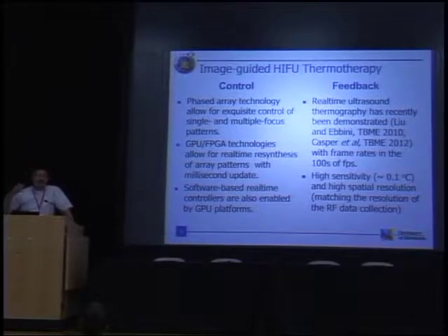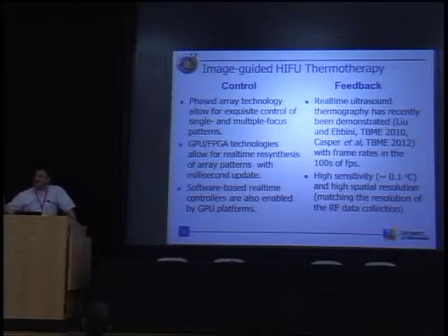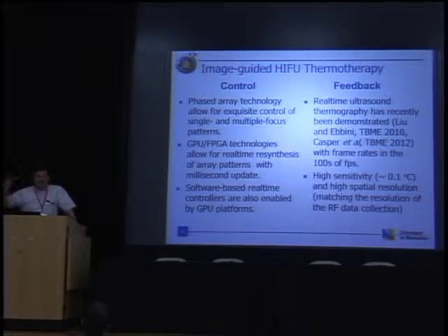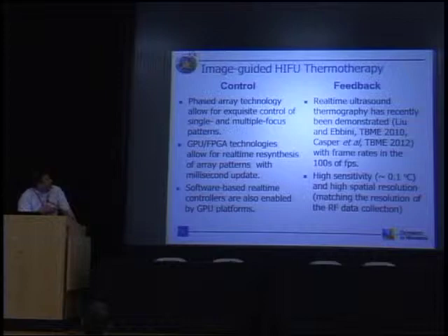We developed these nice algorithms for refocusing arrays, but the circuitry, just simply the error in quantizing amplitude and phase, for phased arrays was larger than anything you can hope to correct. So now we have very, very fine control of phase and amplitude. We have very fine control of spatial and temporal dynamics of heating as well as imaging that's happening on this side.